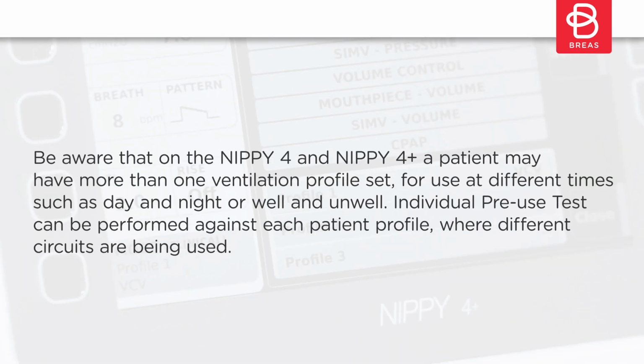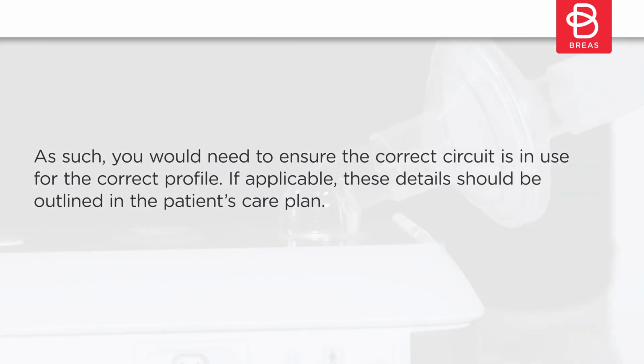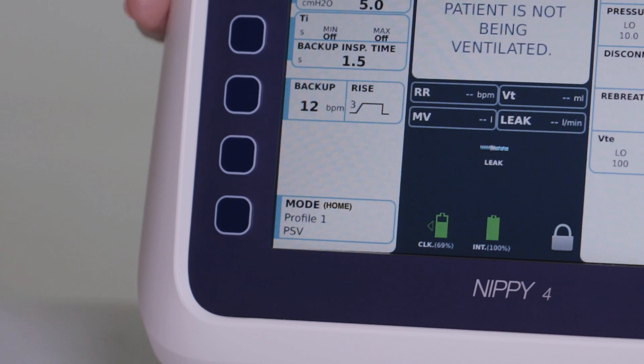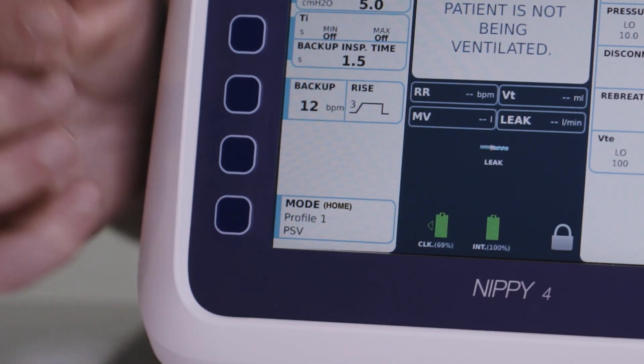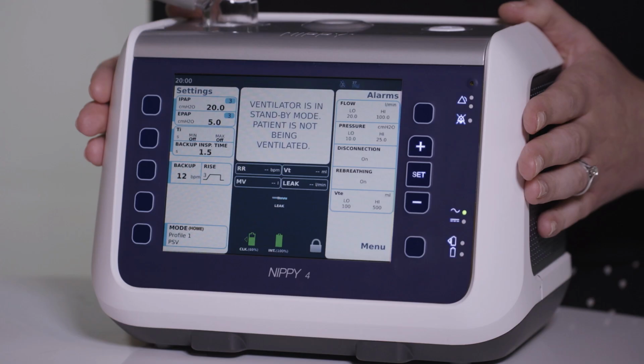Be aware that on the Nippy 4 and Nippy 4 Plus, a patient may have more than one ventilation profile set, for use at different times such as day and night, or well and unwell. Individual pre-use tests can be performed against each patient profile, where different circuits are being used. As such, you would need to ensure the correct circuit is in use for the correct profile. If applicable, these details should be outlined in the patient's care plan. Profiles are accessed and changed using the Mode button at the bottom left on the front of the device and will be discussed later in this video.